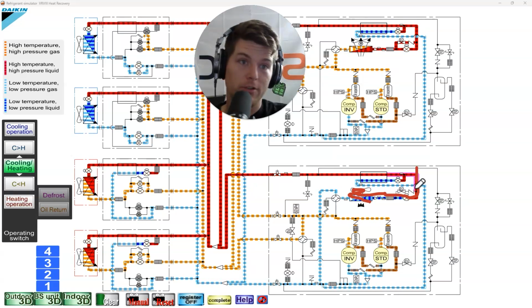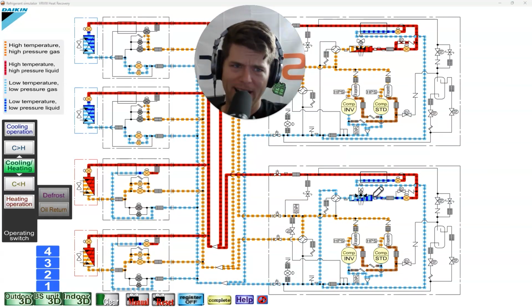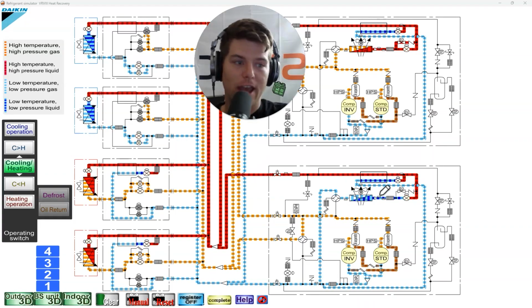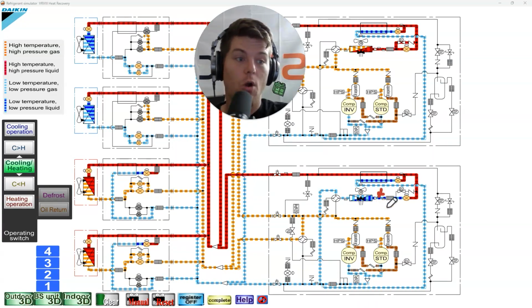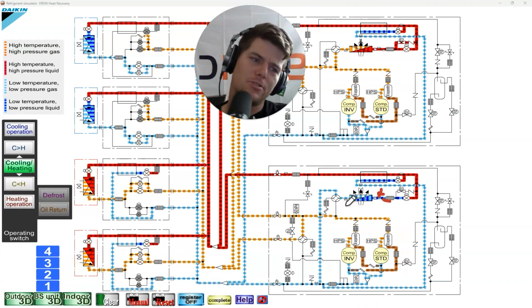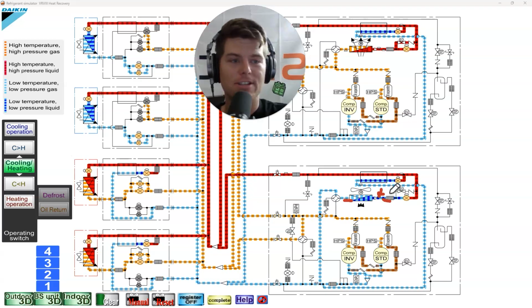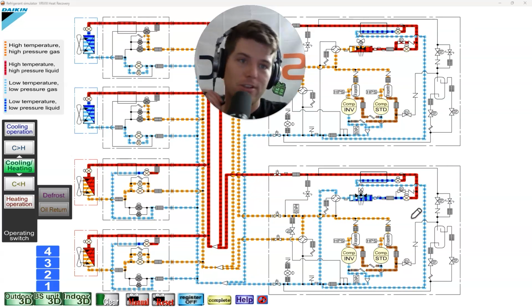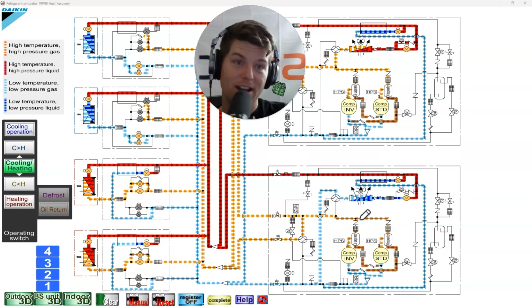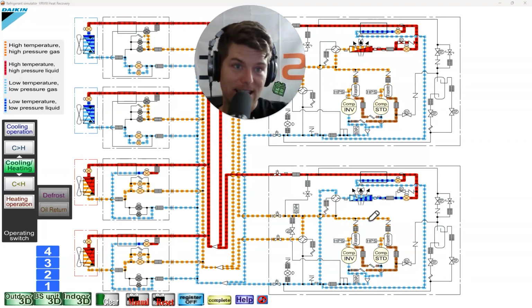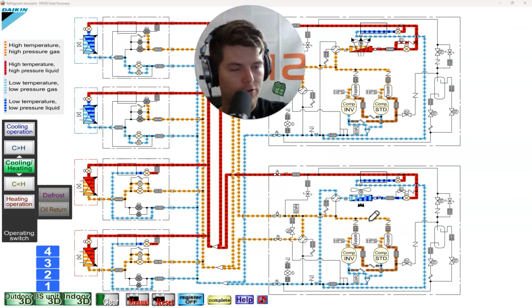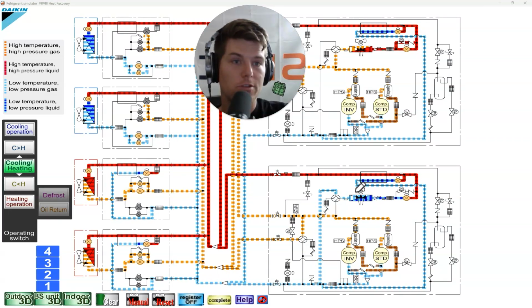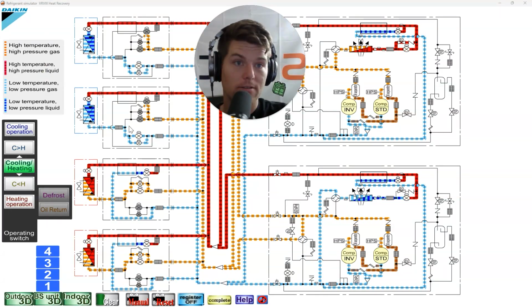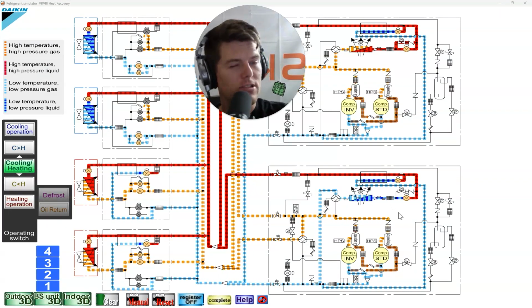How do I know if something is flowing through a coil? You ask. Silly you. I look at this temperature sensor here, or this temperature sensor here, or this temperature sensor here. I've really got a wide variety. I've got 3 sensors. What do we know about refrigerant that's not flowing through an evaporator coil or coil in an evaporative state? We know that it should match TE when it closes, because remember, refrigerant's boiling off. But then eventually, with the fan running, it should match what? Ambient conditions. Let's take a look at that.